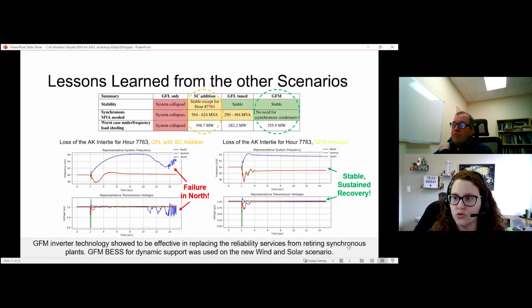We were able to address the stability problem with some synchronous condensers, but we got the best performance when we modeled our batteries for support as GFM batteries. We were able to achieve stability in the most critical cases across the other scenarios, so because of that, we applied the same approach here in the wind and solar scenario, which had much more challenging hours.